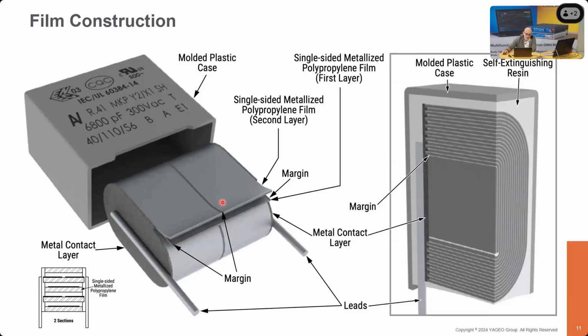Because you need to have a contact to the windings, there's a metallized layer applied on the left and right, or crown side, of the winding, which we call the bobbin. This is called the Schoopage layer. The trick is to deploy spread liquid metal on a plastic material that typically melts at 130 to 150 degrees Celsius, so that's not an easy process. It also means you cannot make it unlimited thick, which limits the contact you can apply to get some kind of termination.